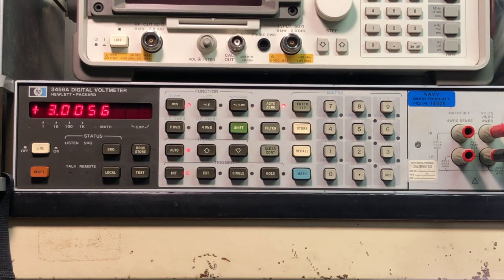Now that's the only voltage that could be adjusted, but it looks well within spec, no problems at all. 3.005, little fluctuation, 6 or 7 there. No problems. The specification in the service manual calls for 3.00 plus or minus 0.02, so well within spec. 0.02 would be 20 millivolts, so not a problem there. So all the voltages are looking very good, no issues at all.